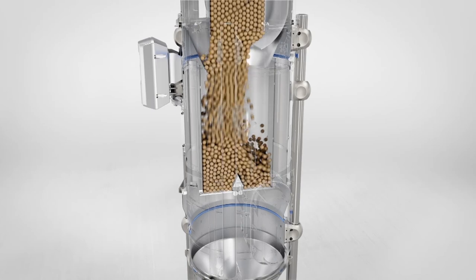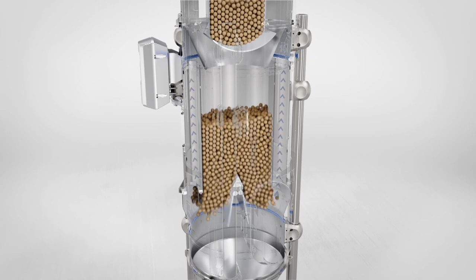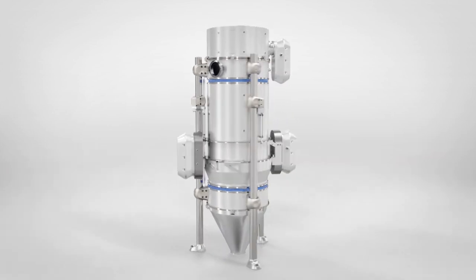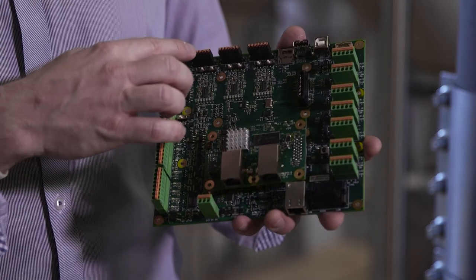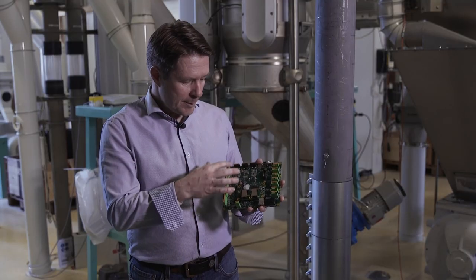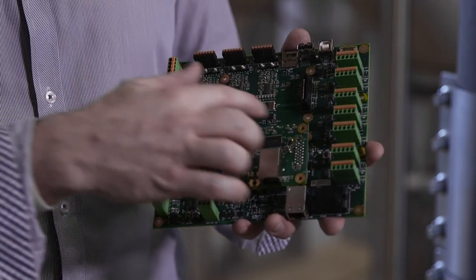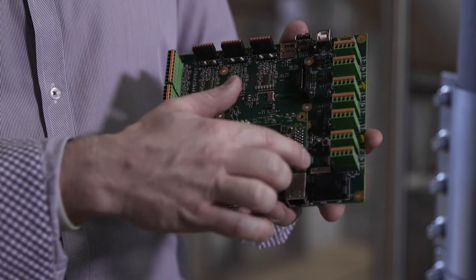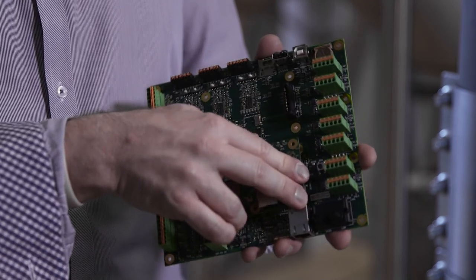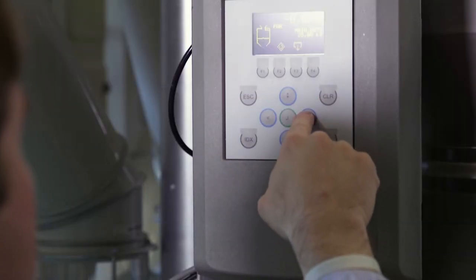Tubex has a built-in differential pressure sensor, which makes outer air circulation pipes obsolete. To reach this goal, Buehler engineers developed a completely new control system. We have three independent load cell converters to be more precise and get more information out of the process. We have also developed a new communication board for host system connection or IOT applications.